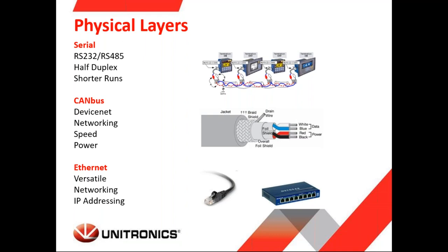With RS-485 you could have one-to-one communication, but you need to account for termination. If you have more than one device on a network, the end devices need to have a terminating resistor, which allows the line to know that the message is ending at that particular point. If you do not set termination, you could introduce noise issues into the system.